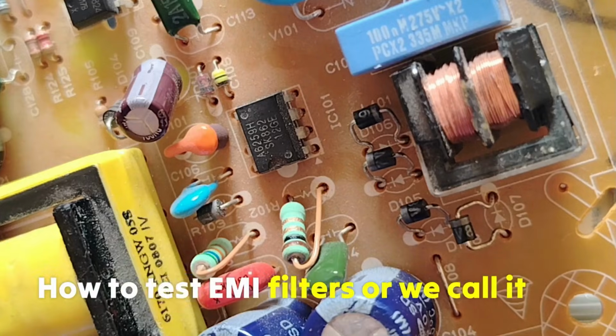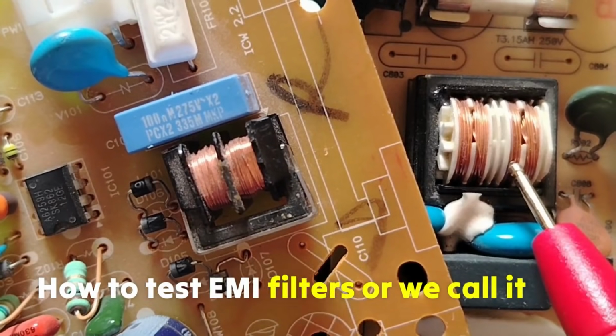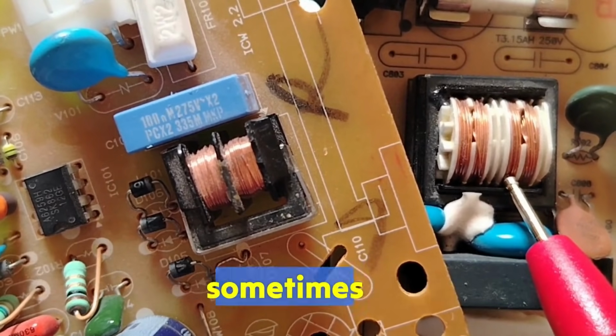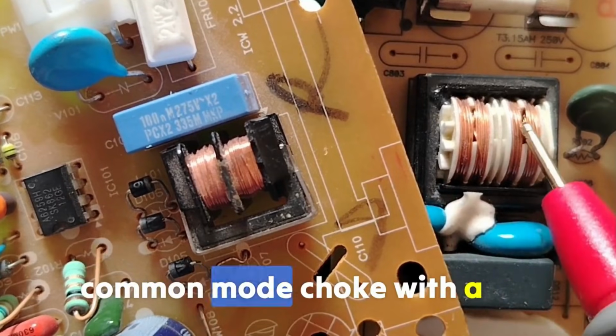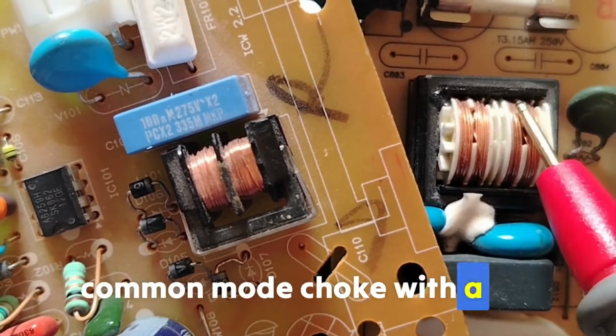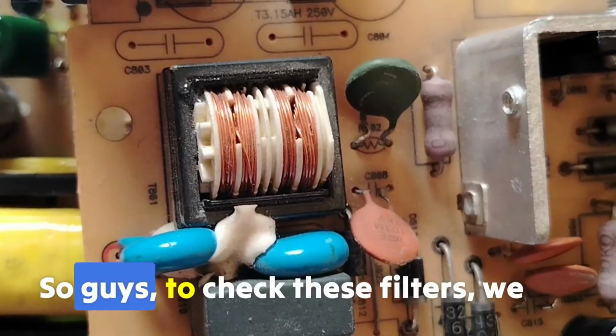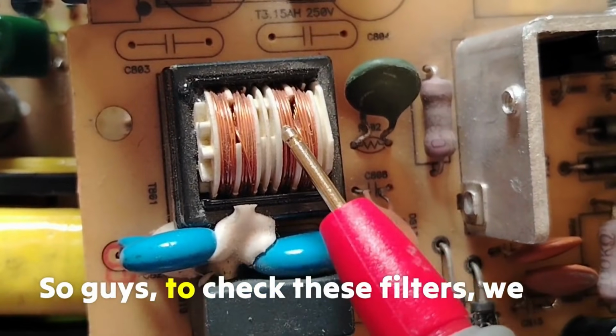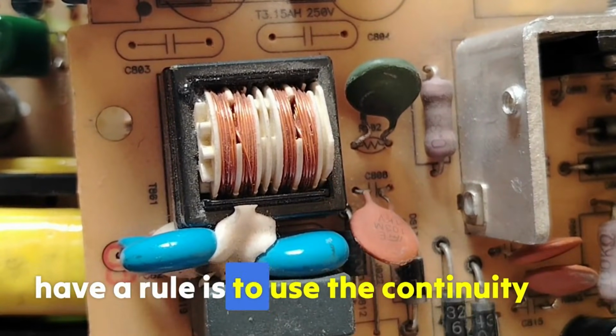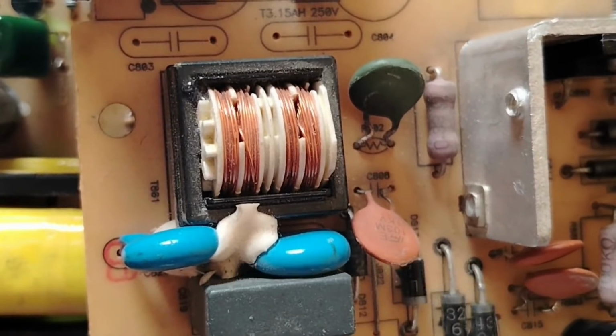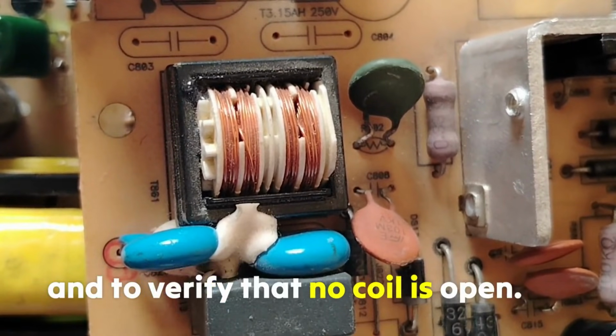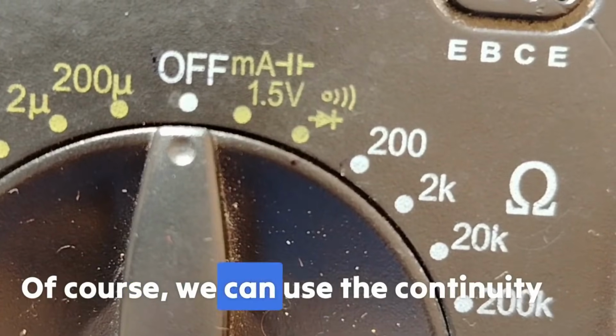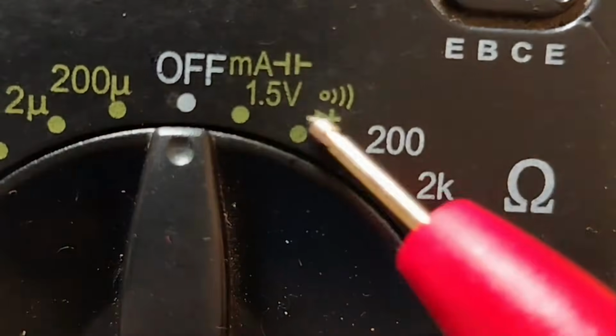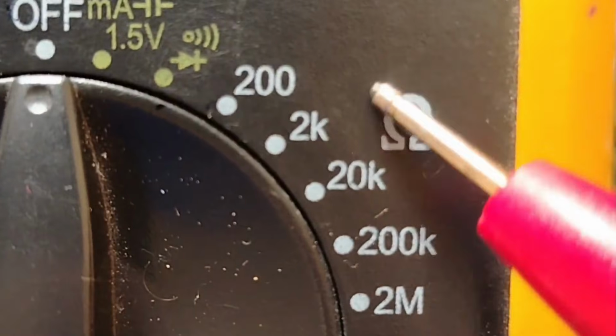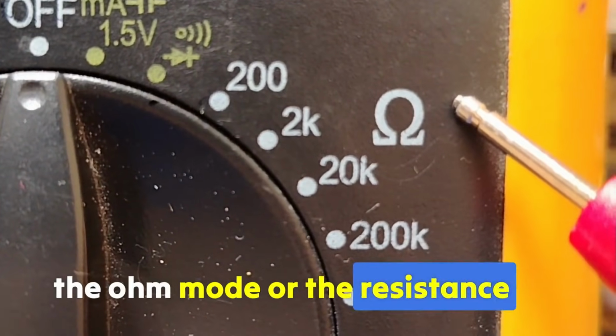How to test EMI filters, or common mode chokes, with a multimeter. To check these filters, the rule is to use the continuity mode and verify that no coil is open. We can use the continuity mode, the ohm mode, or the resistance mode.